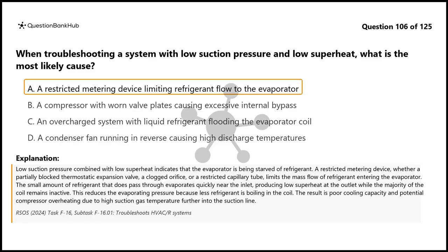This reduces the evaporating pressure because less refrigerant is boiling in the coil. The result is poor cooling capacity and potential compressor overheating due to high suction gas temperature further into the suction line.